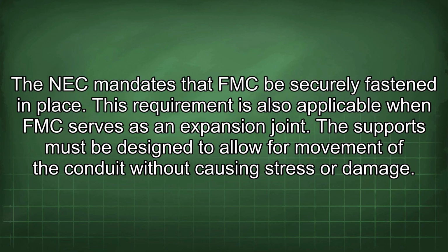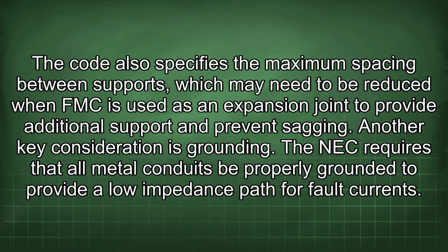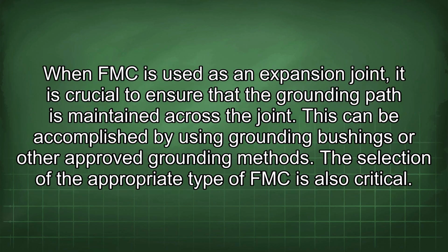The NEC mandates that FMC be securely fastened in place. This requirement is also applicable when FMC serves as an expansion joint. The supports must be designed to allow for movement of the conduit without causing stress or damage. The code also specifies the maximum spacing between supports, which may need to be reduced when FMC is used as an expansion joint to provide additional support and prevent sagging. Another key consideration is grounding. The NEC requires that all metal conduits be properly grounded to provide a low impedance path for fault current. When FMC is used as an expansion joint, it is crucial to ensure that the grounding path is maintained across the joint. This can be accomplished by using grounding bushings or other approved grounding methods.